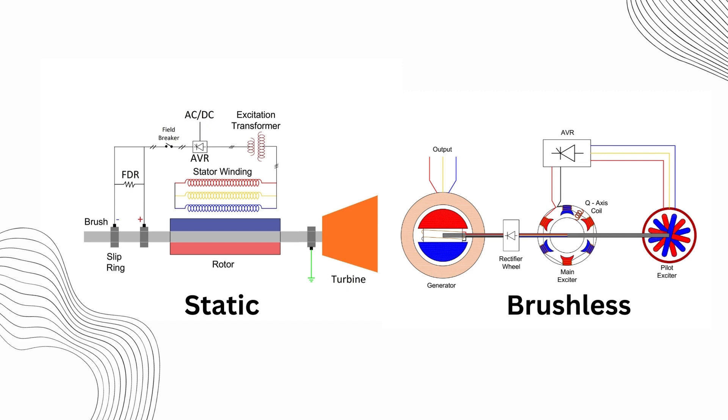However, the brushless system has a significant drawback: slower response time. When you change the set point voltage in a static system, the generator's output voltage changes within 40 to 45 milliseconds. In contrast, the brushless system takes longer because the AVR doesn't control the rotor current directly. It controls the field current of the main exciter, which then goes through multiple stages before reaching the rotor winding. In summary, while the brushless system offers durability and lower maintenance, the static system provides faster response times.